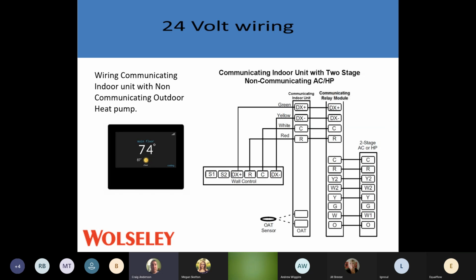Same thing if they have a 2-stage or heat pump system outside. We can hook it onto a communicating system via another relay that we have to hook up downstairs. So we put another relay box downstairs, hook it onto the existing communicating furnace, and then we can go outside to our 2-stage AC or heat pump. Same thing, have to go upstairs and tell that unit that we've added something to it.